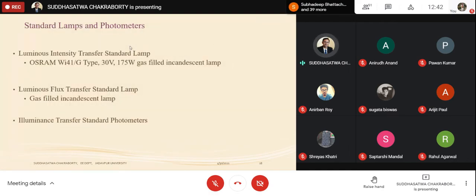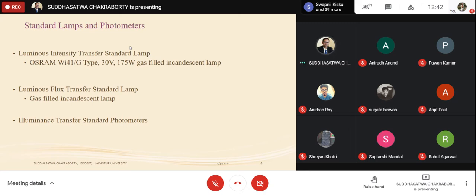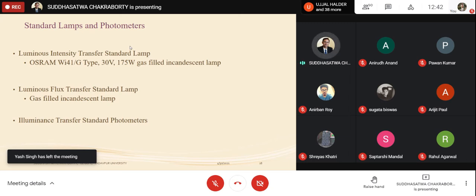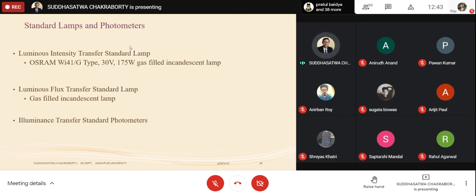For photometric measurements we need standard lamps. Three types exist: luminous intensity transfer standard lamp, luminous flux transfer standard lamp, and illuminance transfer standard detector. A standard lamp is one whose luminous intensity values for different angles are well-known. The luminous flux transfer standard lamp is a source for which flux values are known, and the standard photometer has a known responsivity.